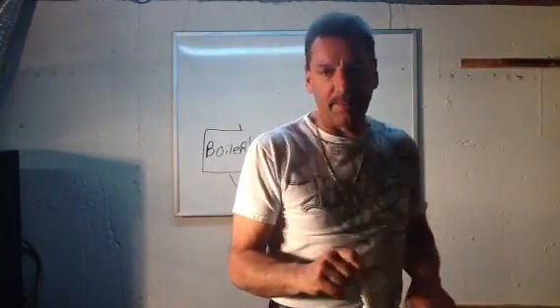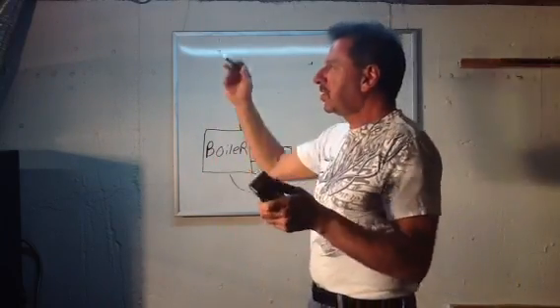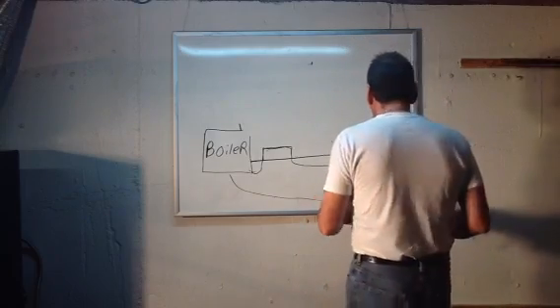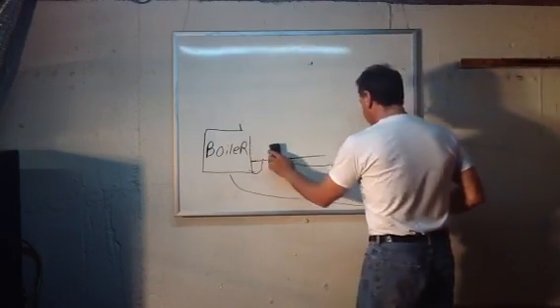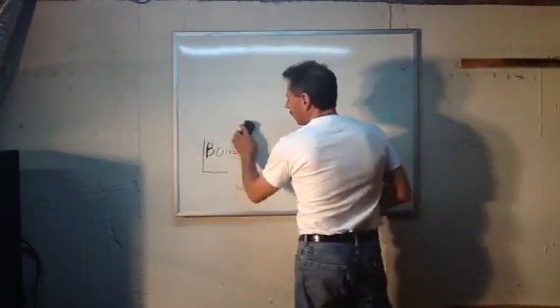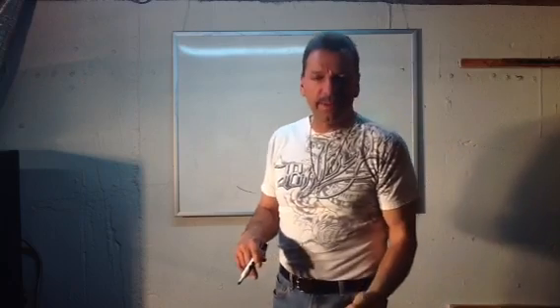If you have a baseboard that's not getting hot, it's a loop system, there's a good chance there's a leak somewhere under the slab. Wouldn't happen in a house where there's a basement because if there's any plumbing, it's going to be dripping down the wall and you're going to see it. But that's the other scenario. If there was all of this in the house and they converted it to baseboard, that's going to be the issue.